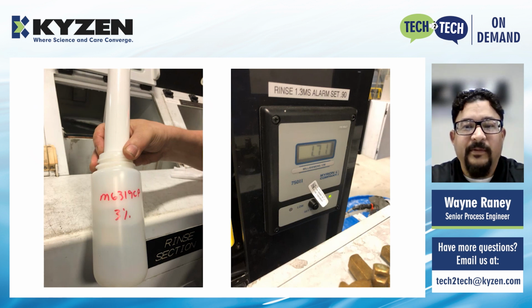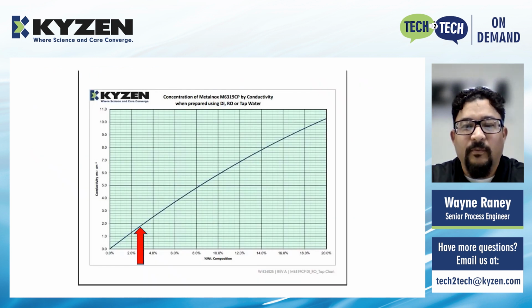Next, we performed a calibration check on the rinse tank. With a 3% solution, we measured 1.71 millisiemens. On the control chart, 1.71 millisiemens corresponds to approximately 3% concentration, as indicated by the red arrow. So it seems that the meter and the probe for the rinse tank is actually reading correctly.